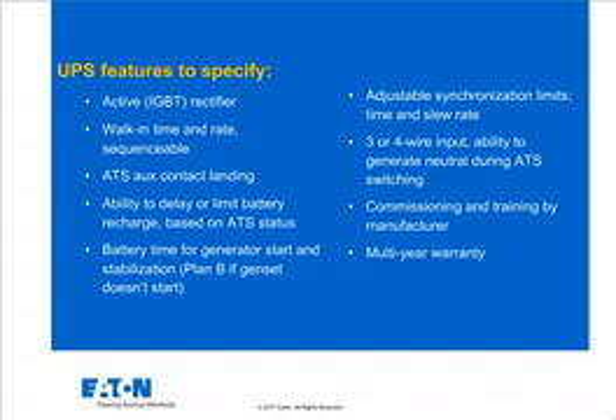Another important one is walk-in time and rate. In other words, if I have a big UPS on my generator and the UPS begins to accept the generator as a load, I don't necessarily want to land the entire UPS capacity on the generator instantly. I want to gradually walk in the UPS so that it doesn't stress the generator and doesn't create a transient for the generator's output load. So one of the things I can do is adjust the UPS's walk-in time from, say, 5 seconds to 30 seconds or a minute or more. I can also adjust the rate. How fast does it walk in and how quickly does it draw power from the generator?